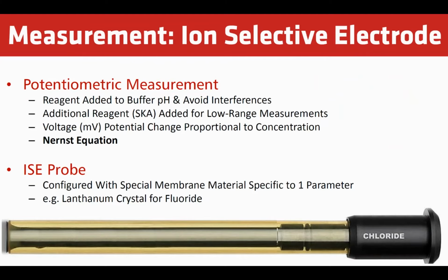We will actually spike the sample with a known concentration of chloride because these probes are prone to drifting. So anything beyond the spike that we put in it is proportional to how much actual chloride is present. So that's a way that we stabilize this. We're always looking at a millivolt potential change proportional to the concentration beyond the spike that we put in it.